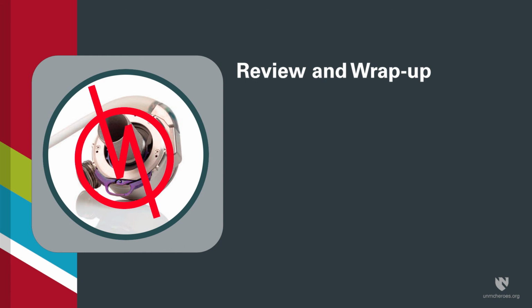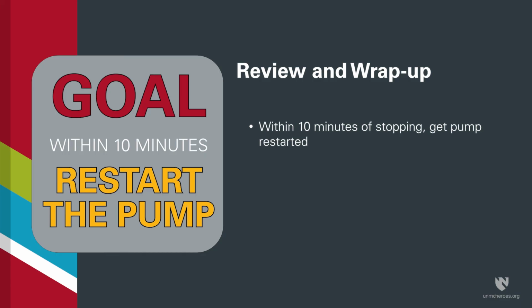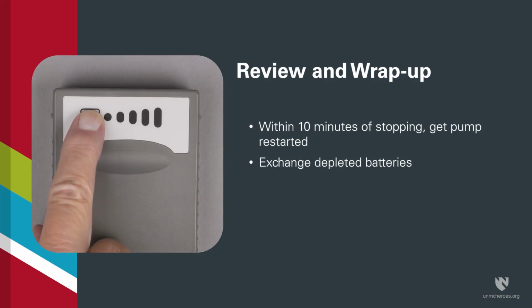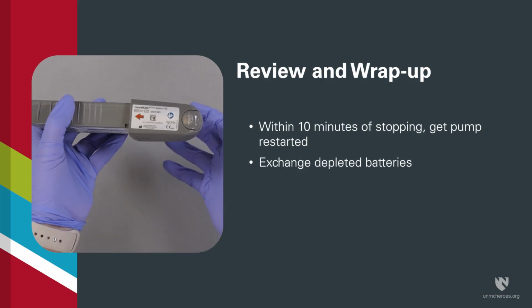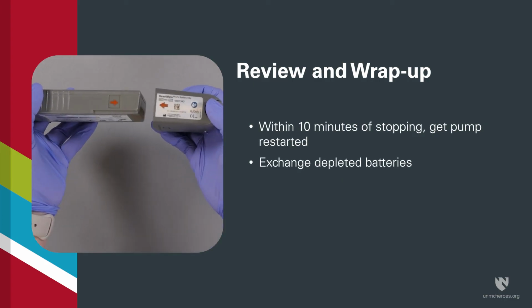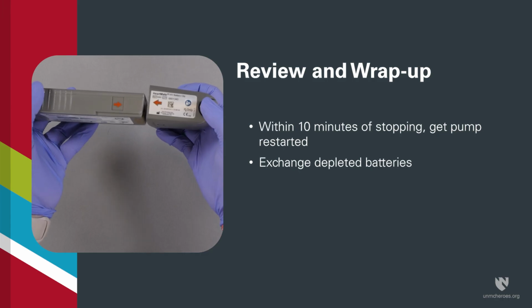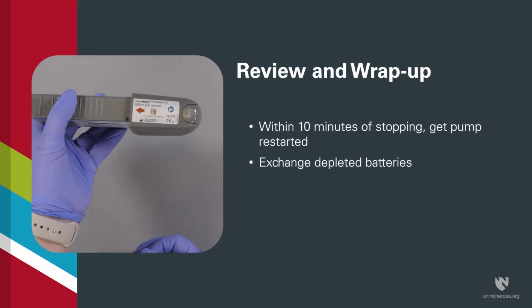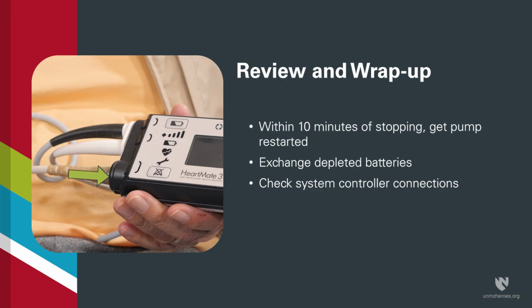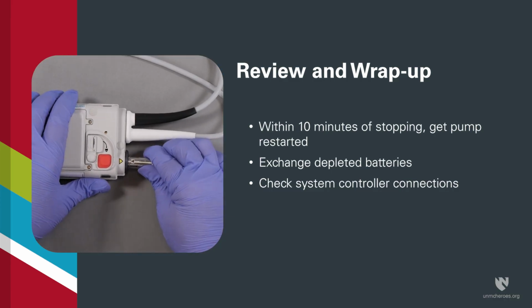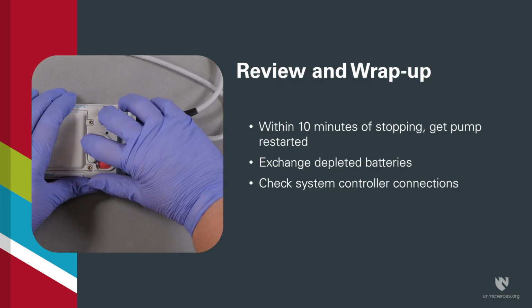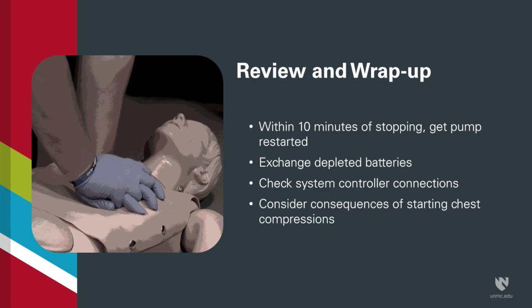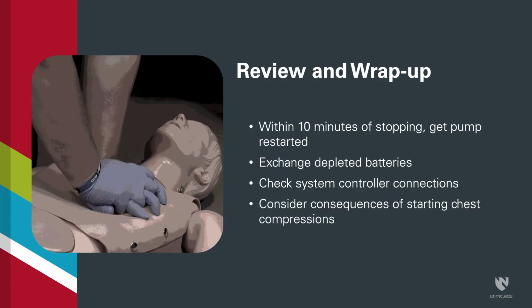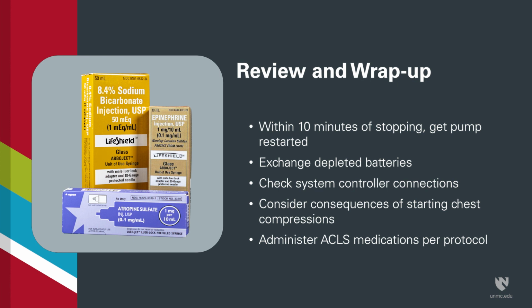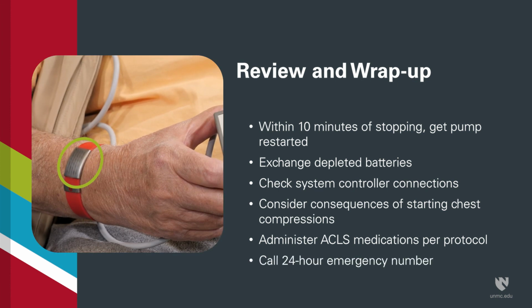In emergency situations where an LVAD patient's pump has stopped, within 10 minutes of stopping, get the pump restarted. Check battery charge and exchange if depleted. Check all connections to the system controller are fully inserted and the safety lock is enabled. Carefully consider the consequences of whether to start chest compressions. Administer ACLS medications per protocol. Call the 24-hour emergency phone number.